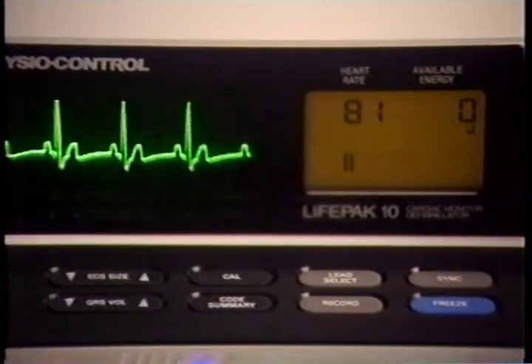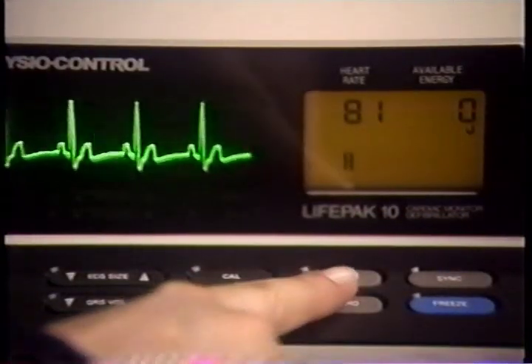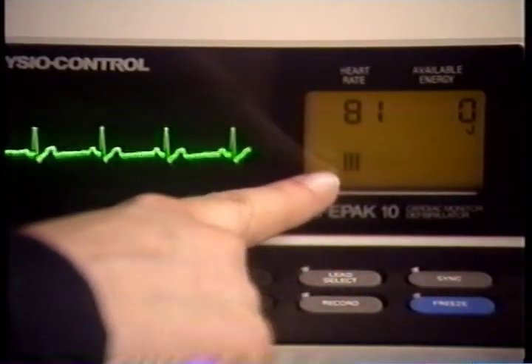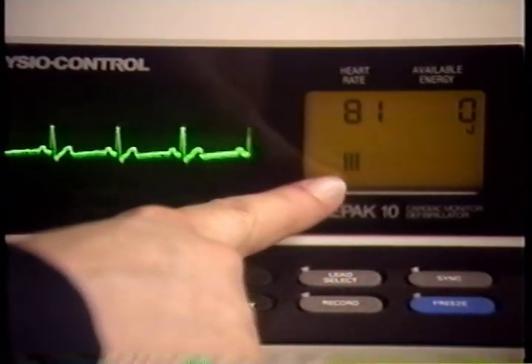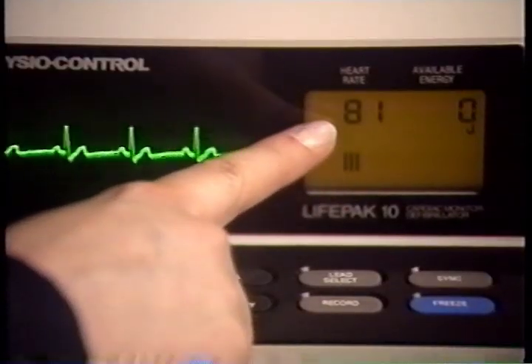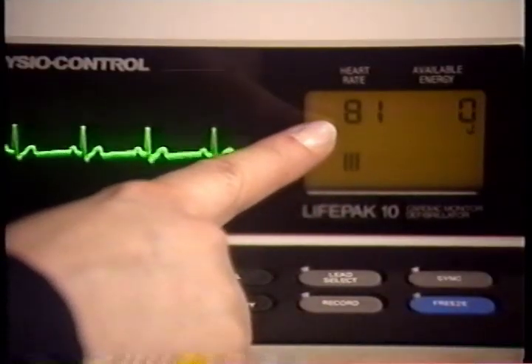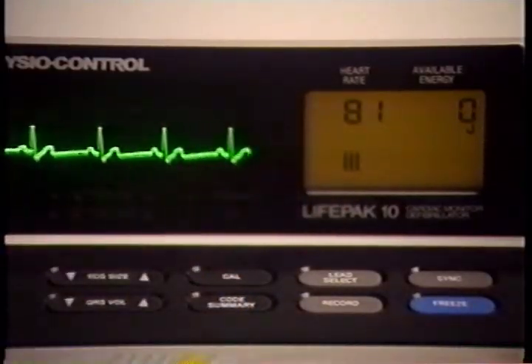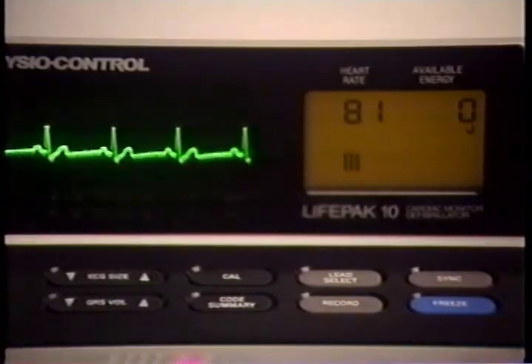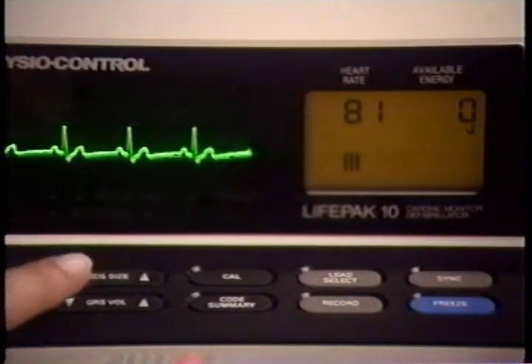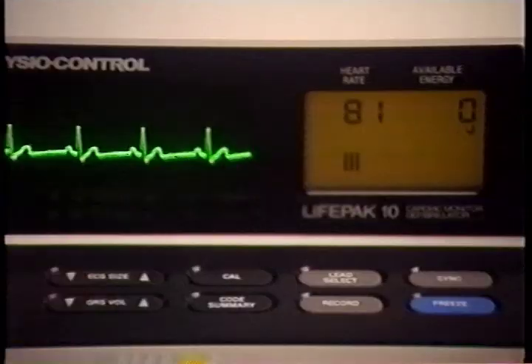Push the lead select button to obtain lead 1, 2, or 3. The lead selection will be indicated on the status display. Also, heart rates of 20 to 295 beats per minute are displayed in the upper left-hand corner of the status display. If the heart rate does not appear, adjust ECG size up or down until it does.